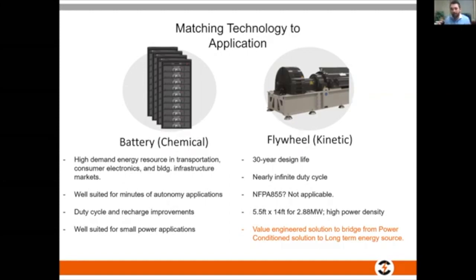Typically, with a static UPS, you use a battery - an electrochemical device, very good technology. I would suggest below 1 MVA we will struggle to compete, very honestly - they're really that efficient, and the price point is very, very good. So what we tend to find is above the 1 MVA, above the 1 megawatt mark I should say, that's where we start to offer all the USPs I'm going to talk about. We don't use batteries, as I said - we use a flywheel.